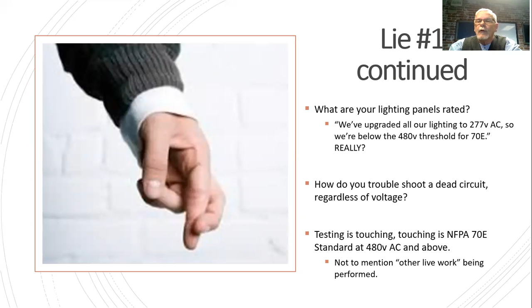Lie number two kind of plays into one: oh, don't worry about it, it's okay, it's de-energized, it's dead. The most important phase of the control of hazardous energy standard on the electrical side, on all sides, is the fact that the person is required to verify that, in fact, they have reached a zero energy state.